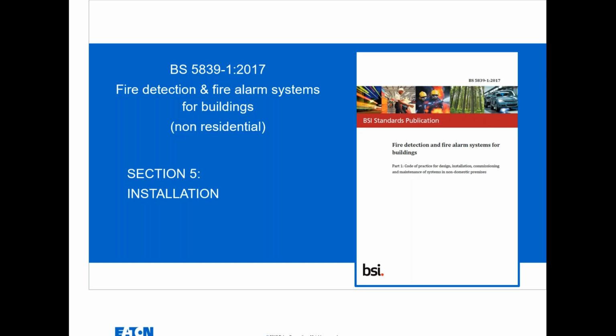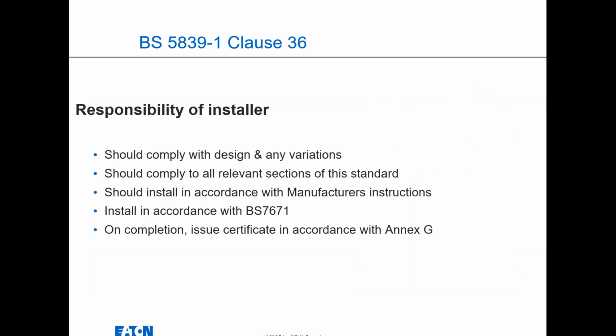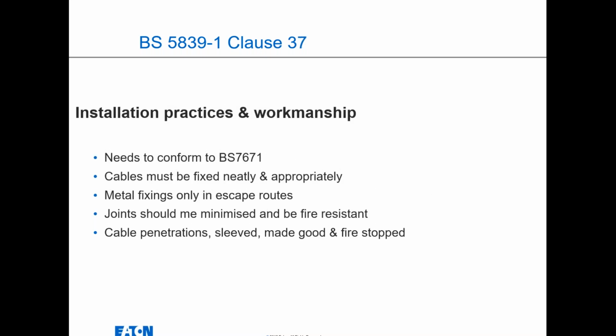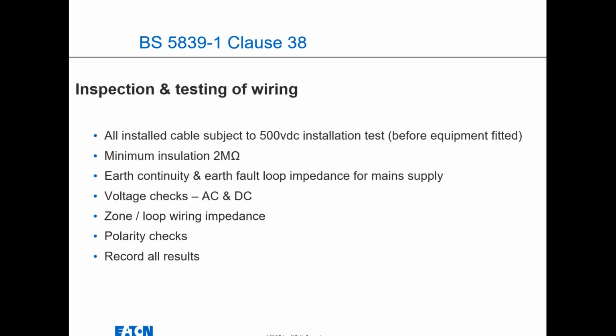Okay, so installation. There are responsibilities of the installer, as we touched on earlier, because they should be looking at compliance with design and any variations. They should be compliant to the relevant sections of this standard in terms of their obligations, and then they should install it within manufacturer's instructions. And then on completion, they should issue a certificate for install. There are obviously installation practices and workmanship, so they need to conform to BS 7671, all metal fixings, etc. And they should again comply with NSI or whatever their governing bodies are. Again, this is all down to installation, volt checking, and bits and pieces such as impedance testing.